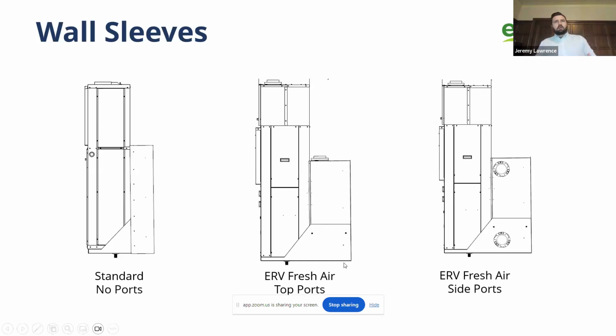So if you're installing a FreshPack unit with the built-in ERV, of course, the ERV or energy recovery ventilator or heat recovery ventilator do need fresh air and exhaust vents to the outside. The benefit of these units is that we already have the sleeve that is exchanging fresh air while the condenser fan motor is running. So we can just use that. We don't need to punch 2 more holes in the wall and further worry about air leakage and penetrations and loss of heat. So there are 2 options, top port and side port. We want to keep the closets as small as we can. So I don't know that we've ever sold a side port unit. The top port is the best way to go to keep your closets as small as possible.